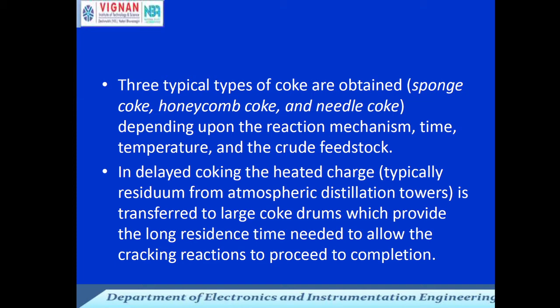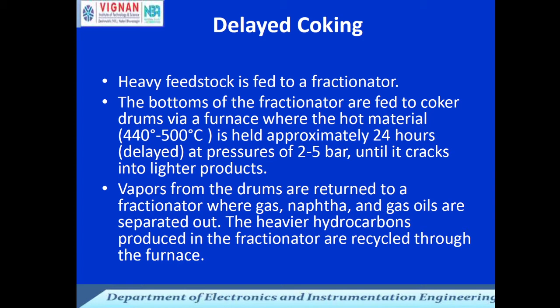Heavy feedstock is fed to a fractionator as we have seen in the block diagram. From the bottom of the fractionator, it is fed to the coker drum via a furnace, where the hot material is maintained at 440 to 500 degrees centigrade and held for approximately 24 hours at a pressure of 2 to 5 bars until it cracks into lighter products. The vapors from the drums are returned to the fractionator, where gases, naphtha, and gas oils are separated from each other. The heavier hydrocarbons produced in the fractionator are recycled through the furnace.